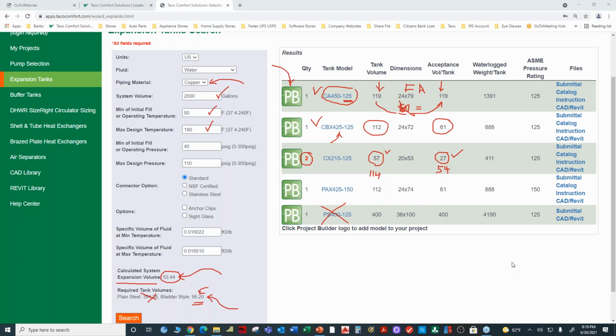You used 180 degrees for your maximum design temperature. Correct. Someone asked, this is obviously a hot water temperature, but I do a lot of chilled water designs. Should I use 60 degrees, or what would you recommend for chilled water piping design? For chilled water for New England, I would typically use 110 degrees. So, oh wow, what are you talking about? The water's not going to get to 110. Well, believe it or not, it can get quite hot.